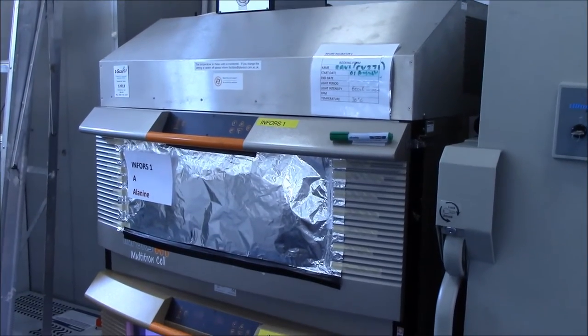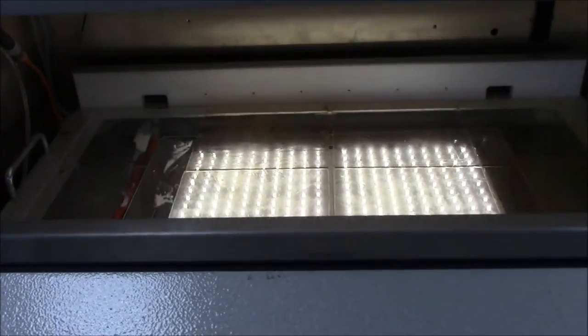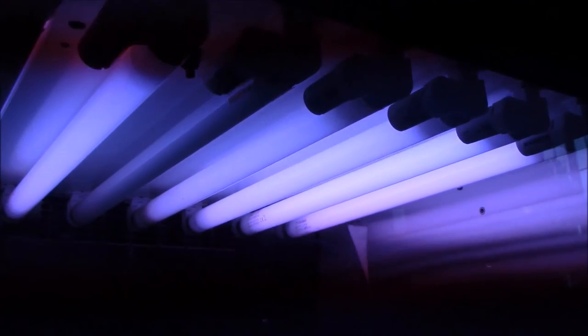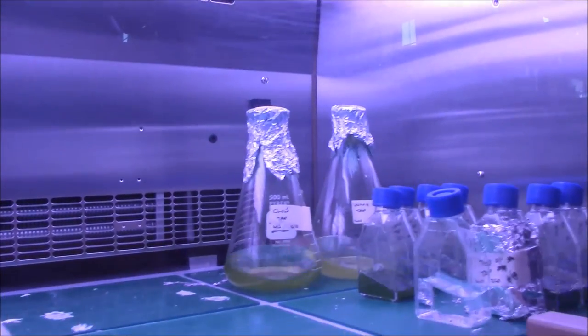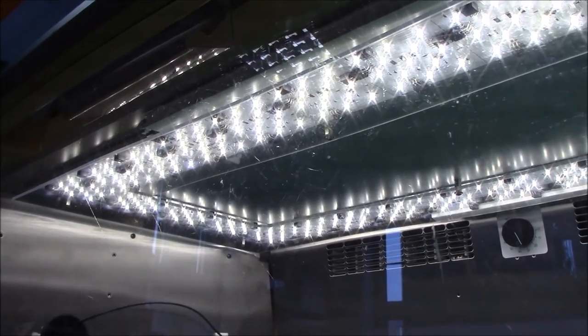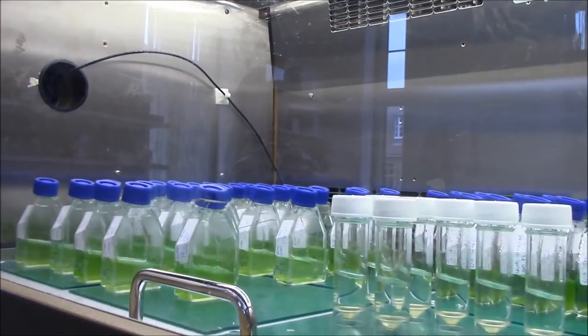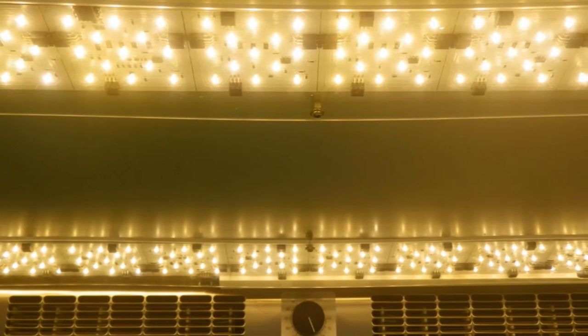Initially, a mule unit was produced by Infors which had high performance LEDs underneath where the algae flasks are placed. Algae grown in this shaker were tested for metrics such as dry mass, chlorophyll concentration and optical density, and results were compared with algae cultures grown in standard incubation shakers. The specifications of the optimum growth conditions were passed back to Infors to fine tune the next prototypes. It was much simpler to fit these LED arrays, and the new system offers improved consistency of light level over the tray area. Setup is also easier as LEDs can be dimmed with an illumination dial. The electricity usage demanded by the lights has been more than halved, and the new LEDs produce less heat, so even more electricity is saved as the unit chillers don't have to work as hard.